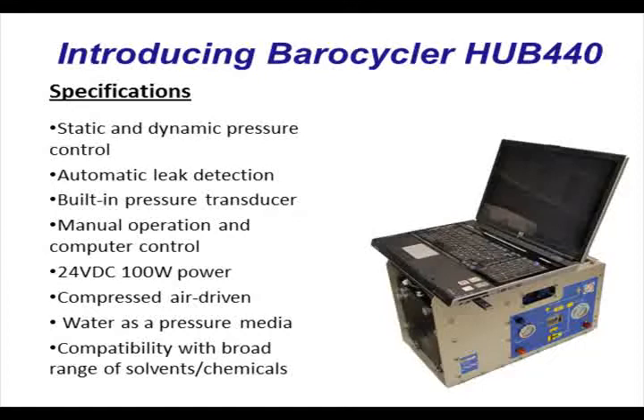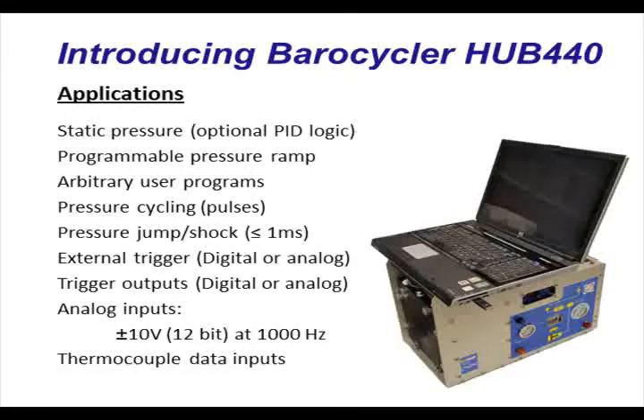It allows you to collect the pressure and temperature data and interfaces with industry-standard equipment to make automation a snap. The instrument is capable of static and dynamic pressure control, performed manually by the operator or driven by a computer program in an unattended mode. It uses a low-voltage power supply and compressed air as input, creating pressurized water as an output.